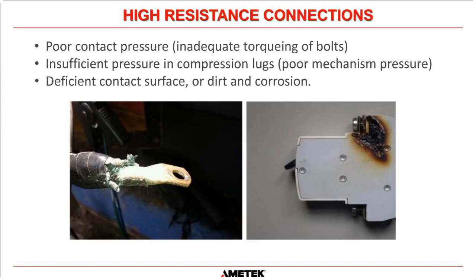You can see this one on the left. That looks like a strand that should be inside the lug. So that's a poor mechanical pressure. And it could also be that this wasn't squeezed hard enough, and the wire strands are kind of loose inside that compression lug. So the connection between this lug here to the wires inside is not quite as good as it should be. And the other thing that this picture shows is you can get corrosion here, dirt and corrosion on the contact surface. So that can cause high resistance connections.